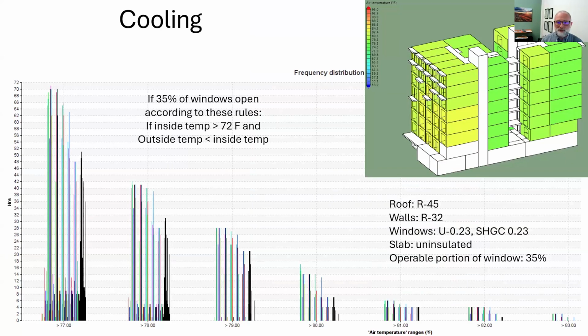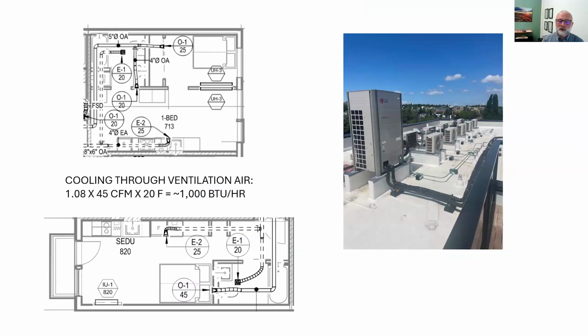We analyzed the potential for overheating in the building to evaluate the need for additional cooling in the apartments. Based on the exposure and the shading, most of the apartments remain comfortable for most of the year. However, because of the windows and the exposure of some of the units, the owner decided to add air conditioning to some of the apartments. In this case, small ductless heat pumps were added to 12 of the apartments that were vulnerable to overheating from solar gain. For the rest of the apartments, cooling is supplied only through the ventilation air.